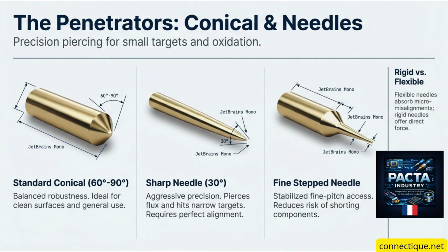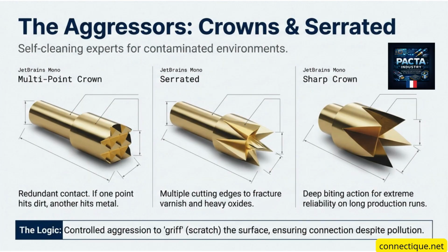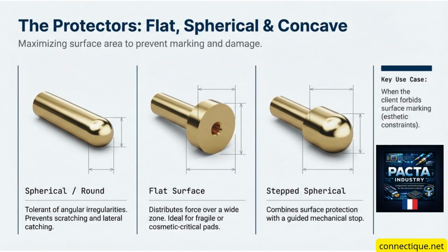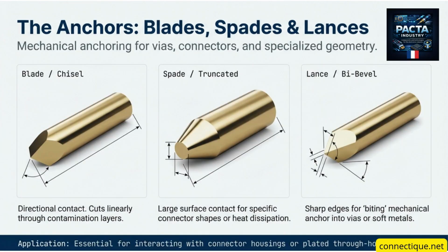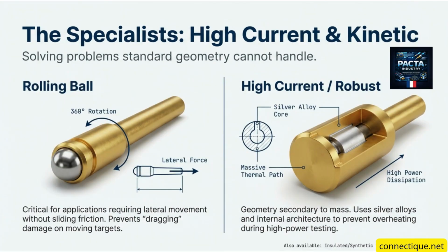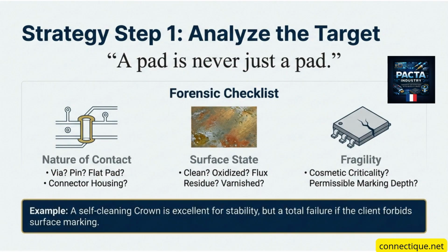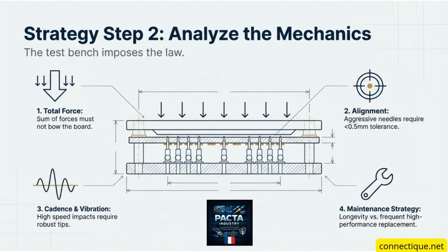It's a balancing act. Okay, and then step 2 is the mechanical environment. Yeah. The bed of nails. Right. In a vacuum fixture, you might have hundreds, maybe thousands of these probes pushing down at once. The total force is massive. If you use extremely sharp needle-like probes and your alignment is off by just a hair, they'll just snap. They'll snap or bend. And a bent probe shorting out against a neighboring component, that's a catastrophe. So if you have a wobbly machine, you need a tougher tip. You switch to a wider angle cone or a step tip to handle the environment.